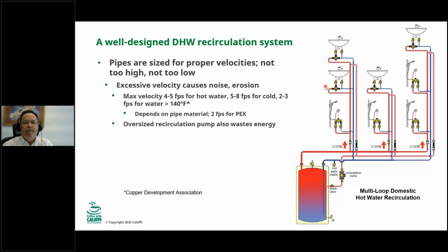And there are references, like the Copper Development Association has references that say for hot water, 4 to 5 feet per second, 5 to 8 feet per second for cold water. And when you are above 140, lower that velocity to 2 to 3 feet per second. So velocity is a very important consideration in designing and sizing your piping. And for PEX, I saw a few references that say 2 feet per second for PEX. I think Max knows about that too. That's what I found. I haven't seen any other numbers for PEX piping, but even lower.